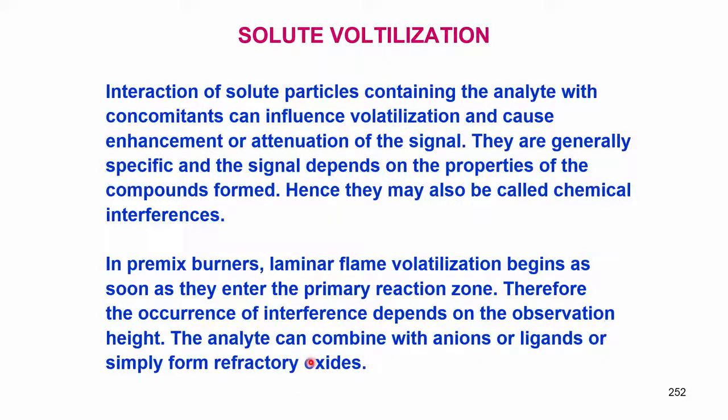If the refractory oxides are formed, they do not dissociate. So, the absorbance will be absolutely nil or negligible. So, we may not know, whenever we are determining a substance containing aluminum or any other refractory metal, chromium, vanadium, tungsten, all these things, they may simply form the oxides, and these oxides do not dissociate. Free atom concentration decreases, absorbance decreases, very simple.